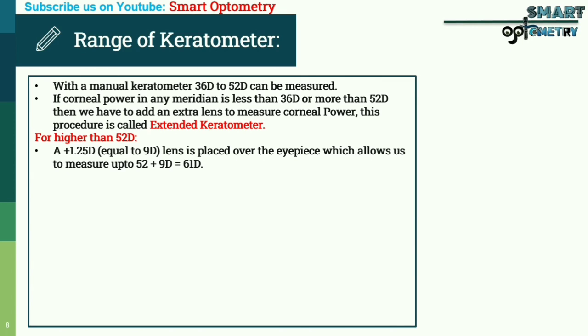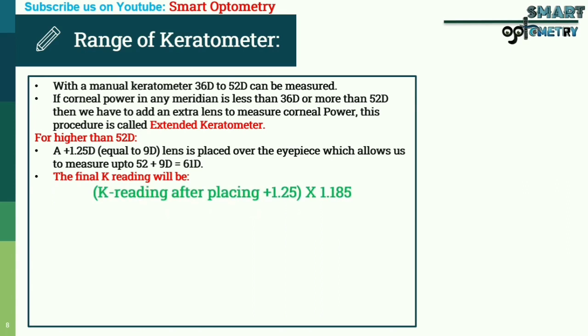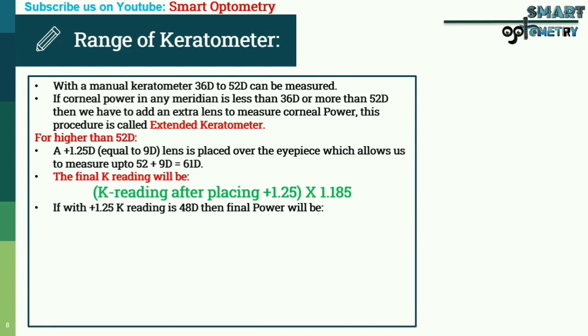measure up to 52 plus 9, equal to 61 diopters. However, the reading obtained on the keratometer after placing the plus 1.25 diopter lens in front of the eyepiece will not be the actual corneal dioptric power. We need to modify this reading to get the exact corneal power. The formula is: keratometer reading after placing plus 1.25, multiplied by 1.185. For example, if with a plus 1.25 diopter lens the keratometer reading is 48 diopters, then the final power will be 48 × 1.185 = 56.88 diopters.